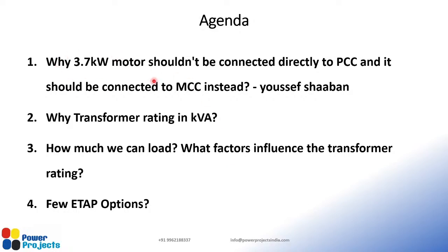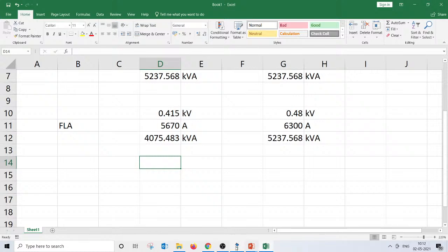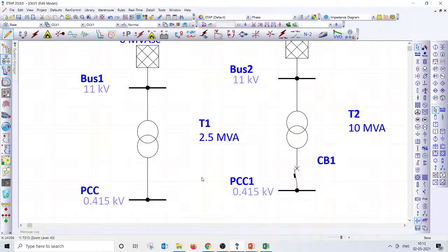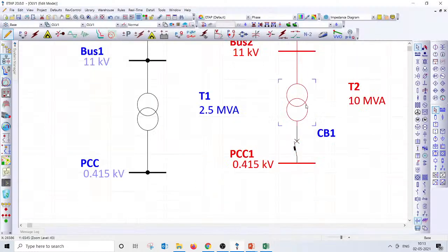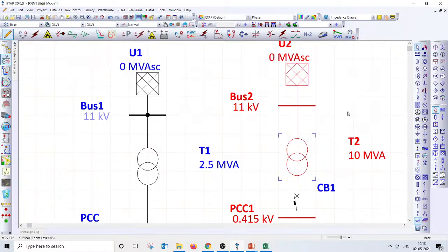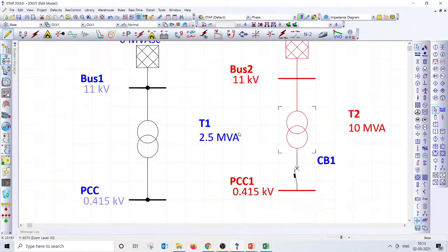Right, so let's come back to this 3.7 kilowatt motor. Let me try to connect this 3.7 kilowatt motor here in the PCC itself. So the answer here, this 10 MVA, is not really right. You can go maximum up to 4 MVA, but even with 4 MVA you also need to check other aspects like the short circuit current and other stuff.